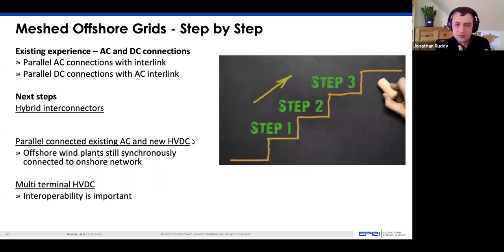You could have parallel DC connections, as I mentioned, maybe 2 to 3 DC connections with 4 to 5 or 6 offshore wind plants all connected together. That way you have a more reliable system compared to just having one wind farm, one cable to shore. You have parallel paths and different paths for the power to flow if you lose a cable, which can happen. That's what we understand at the moment.